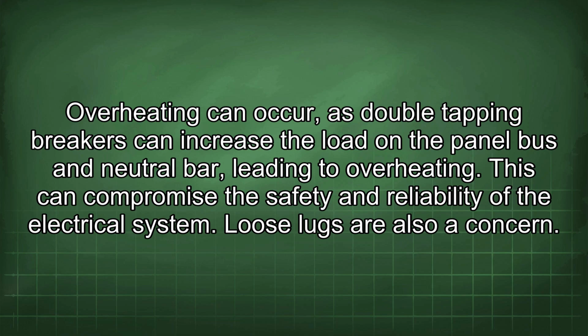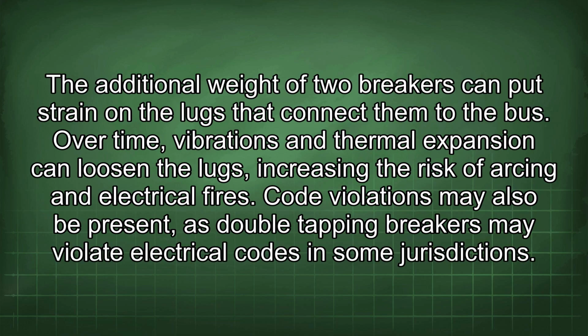Overheating can occur, as double tapping breakers can increase the load on the panel bus and neutral bar, leading to overheating. This can compromise the safety and reliability of the electrical system. Loose lugs are also a concern. The additional weight of two breakers can put strain on the lugs that connect them to the bus. Over time, vibrations and thermal expansion can loosen the lugs, increasing the risk of arcing and electrical fires.